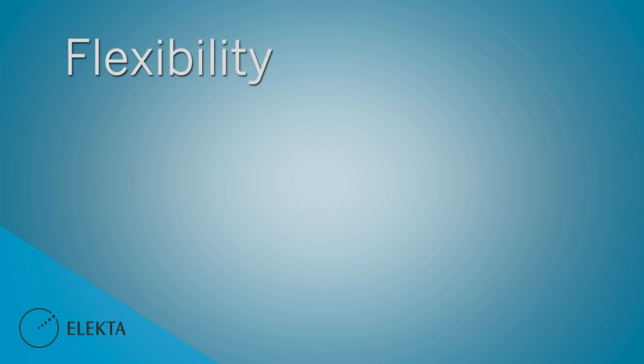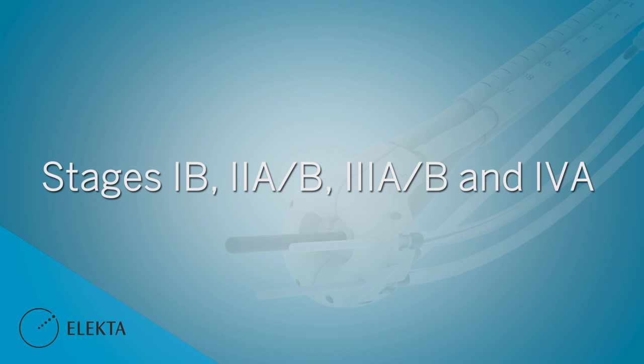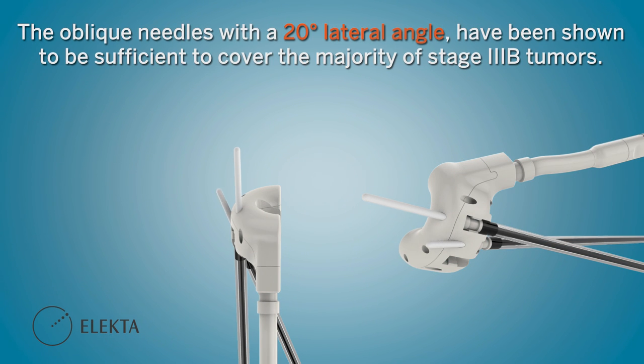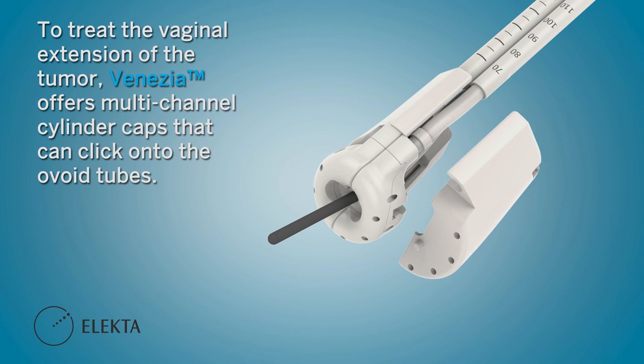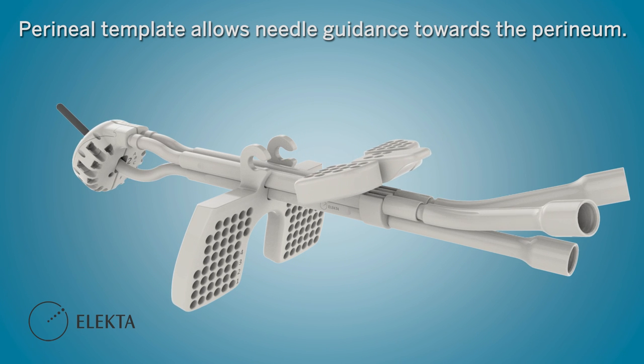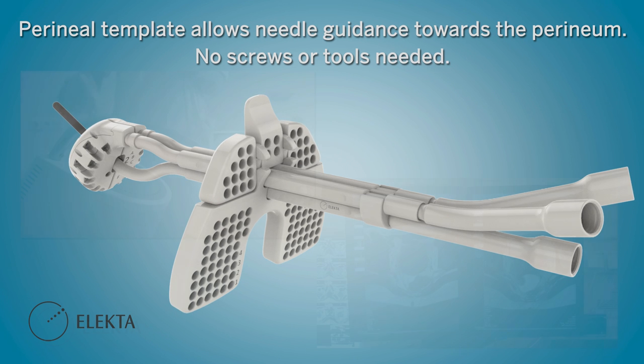Venezia offers flexibility and expands clinical capabilities, providing treatment for various patient groups from stages 1b to 4a. The oblique needles with a 20-degree lateral angle have been shown to be sufficient to cover the majority of stage 3b tumours. To treat the vaginal extension of the tumour, Venezia offers multi-channel cylinder caps that can click onto the ovoid tubes. Venezia also offers a perineal template for needle guidance towards the perineum, even when the vaginal caps are used. The template snaps into place without any screws or tools.